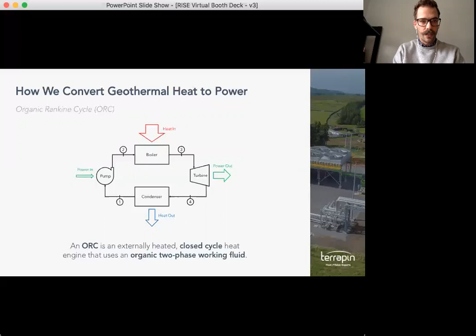The power to run the pumps comes from the ORC facility itself. There's no external power required to operate our ORC power production process, and the unit is entirely self-sufficient. I want to point out that the use of air cooling versus water cooling for our power generation process is, Terrapin believes, a big advantage, especially for water-constrained regions or remote sites.